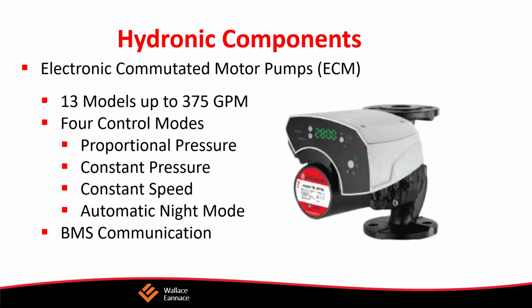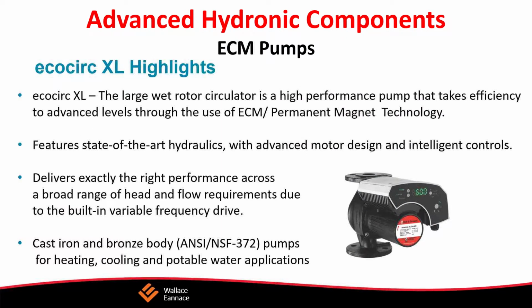And once again, remember there are sensors in there. Because there are sensors in there, there's a variety of control on this. You have a microprocessor built in by definition. So we can now control it for proportional pressure, constant pressure, or adjustable speed control. Proportional pressure means that, for example, if zone valves or Danfoss valves were to go on different systems, the pressure would change, and the flow will automatically reduce proportionally to changes in the pressure. Constant pressure means it'll maintain a constant pressure all the time, adjusting the speed, or it'll set the speed and maintain the speed regardless of pressure.